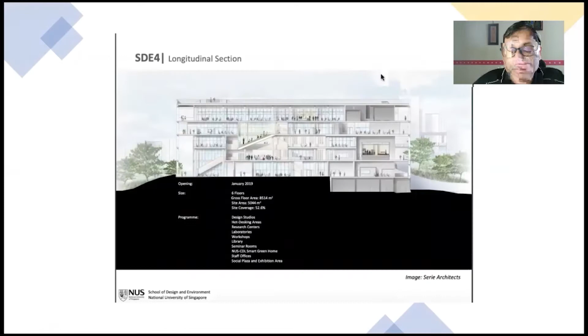So right at the top, we have a reference building which consumes about 1947 megawatt hours per annum. Optimizing the envelope brings it down to about 1600. That's the optimum design in terms of the envelope. Then a high efficiency air conditioning system brings it down to the 1200 mark, and the hybrid system brings it to 820 megawatt hours per annum.